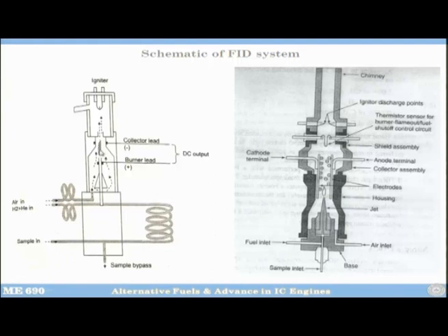So, this hydrogen air mixture will rise and this igniter will apply a spark. So, there will be a flame. Now you will have a steady flame, you have to of course adjust some flow rates, etc. There will be a steady flame of hydrogen helium air mixture, and then it is also getting the supply of the sample containing hydrocarbons at a prefixed flow rate.